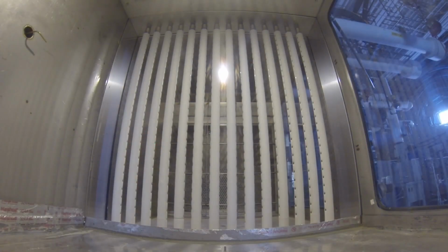Okay, awesome. Are there any inefficiencies or losses that we need to consider in a humidification system? And what are those? Well, when we were looking at the starting and ending point and how much air volume, now we have to consider that's how much we need into the airstream. But we also have the piece of, as you said, inefficiencies. If you're adding steam to a cooler airstream, some of that steam is going to collapse back into condensate or water. It's naturally what happens. You are potentially making steam and then you're dispersing it, and you have to get from point A to point B if they're not next to each other.